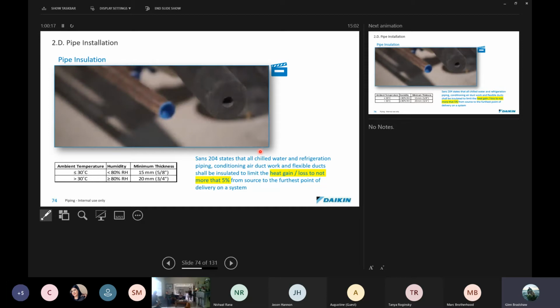The reason for that is that we have incredibly efficient machines, and then we go and throw half that efficiency away by not insulating the pipes properly. And that means that the units then draw more power. And often when the guys say, oh, but the units don't perform according to what your manual says, you can go and find that a lot of your heat gains and losses are through insulation, or through poor insulation. So please take note of that.